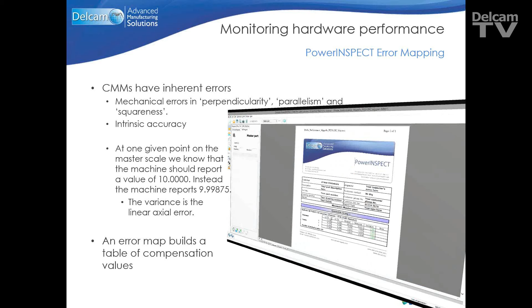Now what you've got in many software packages, called error mapping in PowerINSPECT, is the ability to take the points on the known artifact, like your calibration sphere, and you can then use those values to build an error map, a table of compensation values, and the machine can then use that table of compensation values throughout the inspection program to increase the repeatability of the inspection program. The error will always be there in the CMM, but by having this table of compensation values, you're able to at least apply that error at a consistent rate so that you know that your inspections are repeatable.